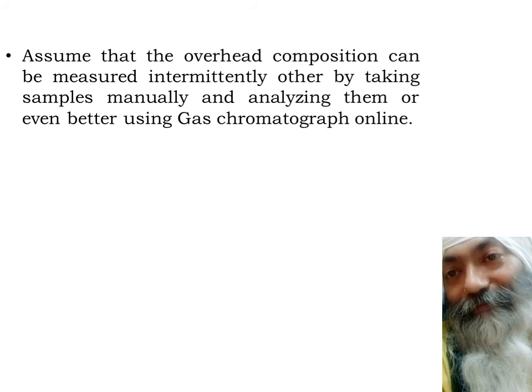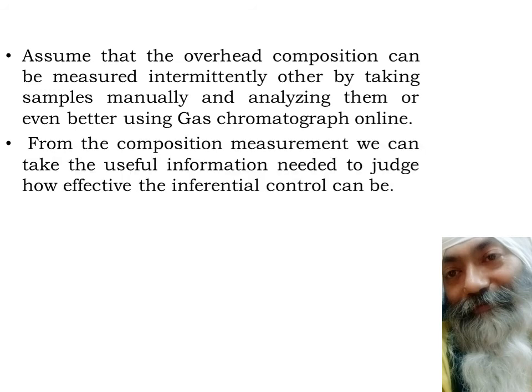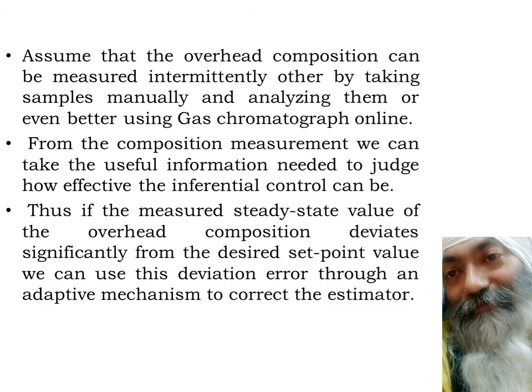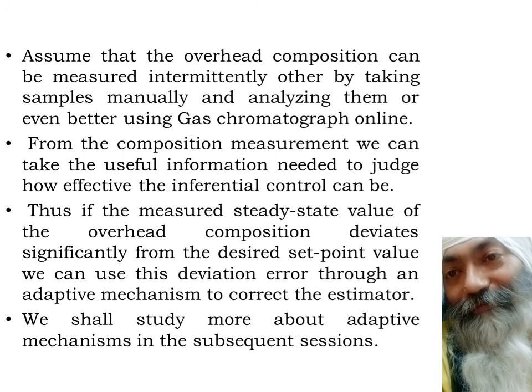When process conditions change, the model changes and the estimator is no longer accurate, so the estimator adapts itself to changes in the process. If the overhead composition is measured using a gas chromatograph, we check the effectiveness of the inferential control, and in case of any deviation we use an adaptive mechanism to correct the estimator itself. This adaptive mechanism and the inferential control estimator — including how it works and how to model it — will be studied in the next part of this video session on inferential control.